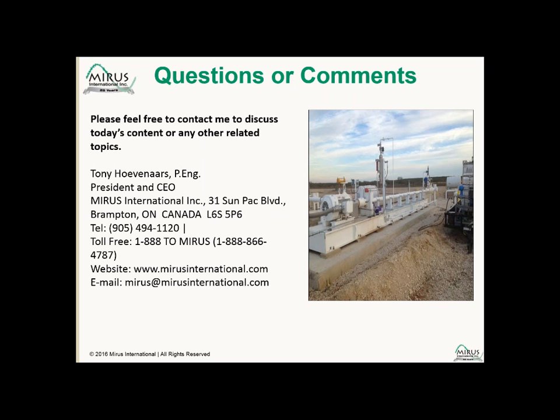I have 4 500 horsepower motors upgraded to all VFDs. Is 2,000 kilowatts required good enough? So a 500 horsepower motor is going to be about 400 kilowatts of load. 4 times 400 kilowatts is going to be 1,600 kilowatts. If you put proper harmonic mitigation, then a 2,000 kilowatt generator will be fine. If you don't, and you just put a 3% line reactor, then you're going to need probably about a 5,000 kilowatt generator. So substantially different. That leads to our next question.